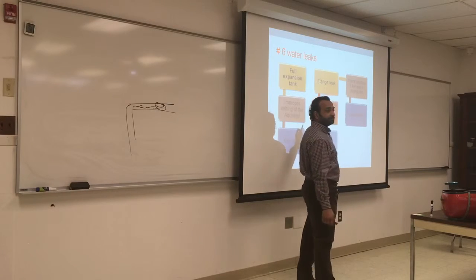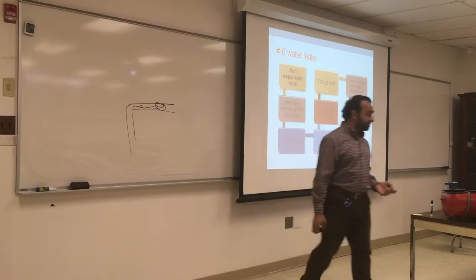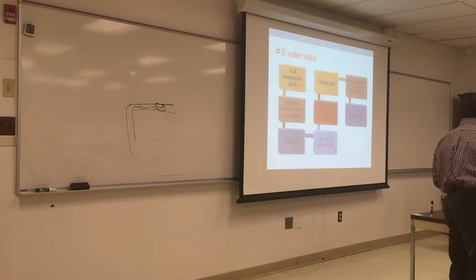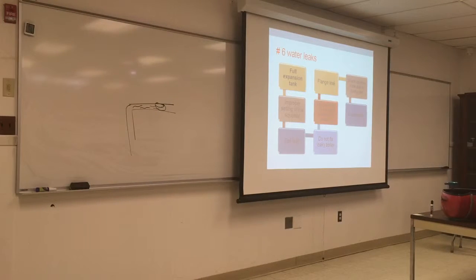The flange, so pumps have flanges and bushing. But if you think about it, this is a circulator, this is a motor, and this is the pump part. If you think closely, there's a shaft going on from the motor to the impeller. There's water in here, and there's no water in here.